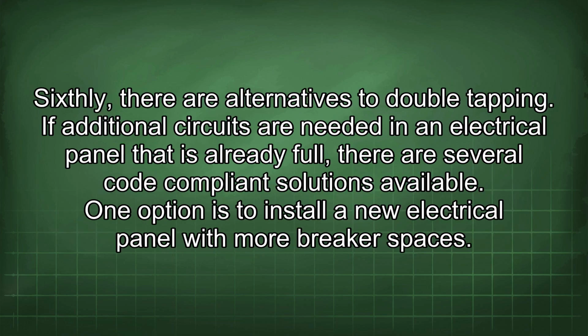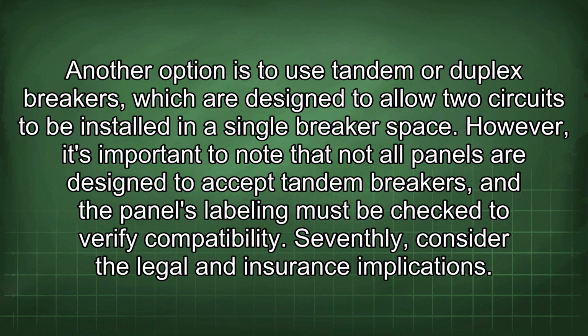Sixthly, there are alternatives to double tapping. If additional circuits are needed in an electrical panel that is already full, there are several code-compliant solutions available. One option is to install a new electrical panel with more breaker spaces. Another option is to use tandem or duplex breakers, which are designed to allow two circuits to be installed in a single breaker space. However, it's important to note that not all panels are designed to accept tandem breakers, and the panel's labeling must be checked to verify compatibility.